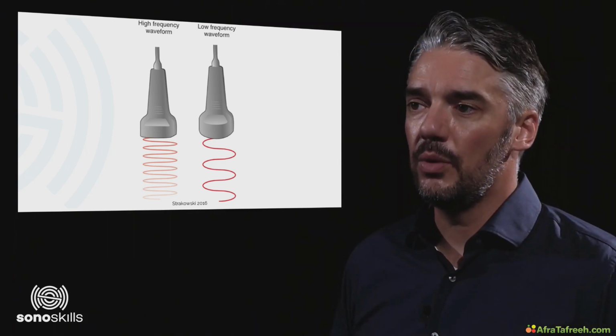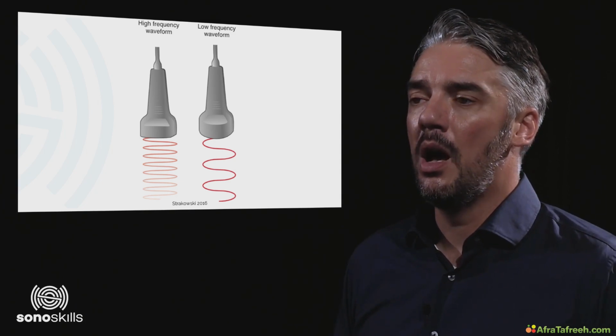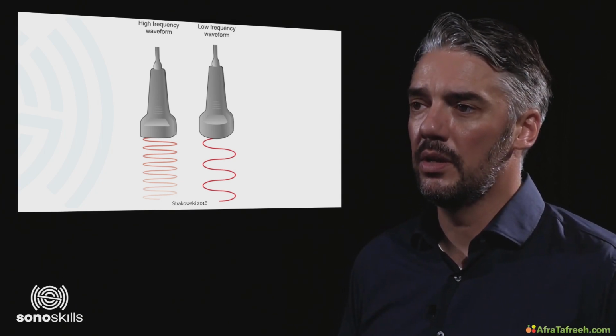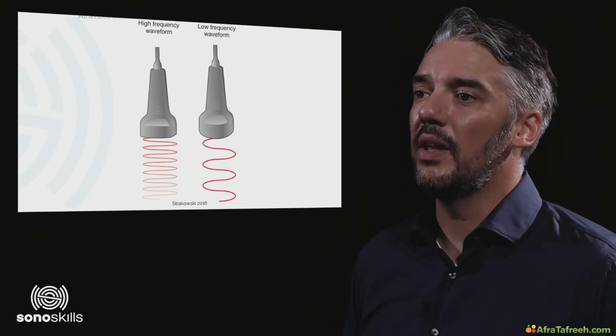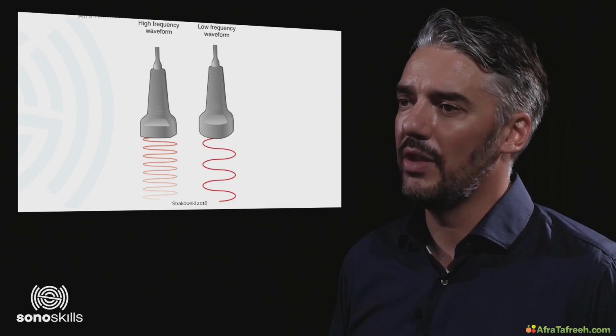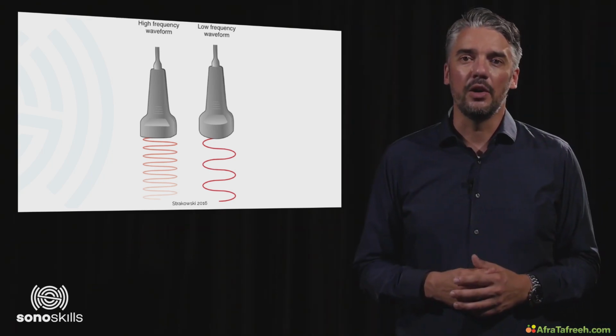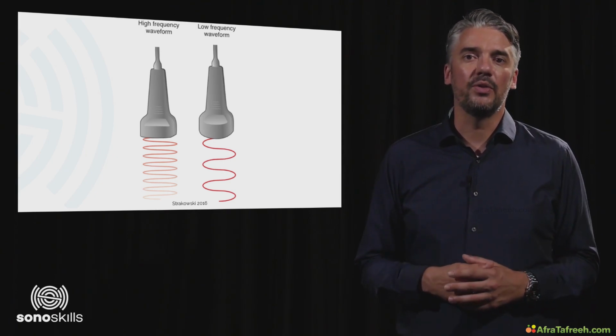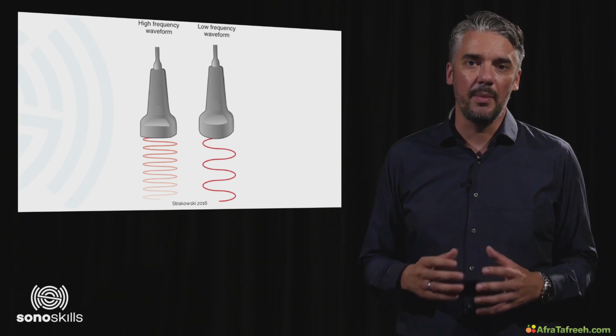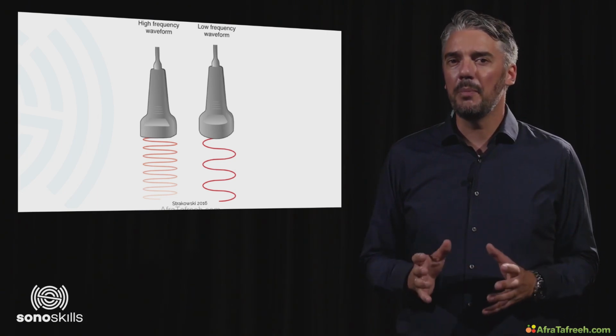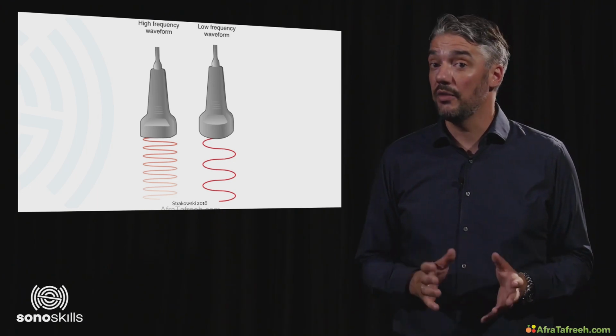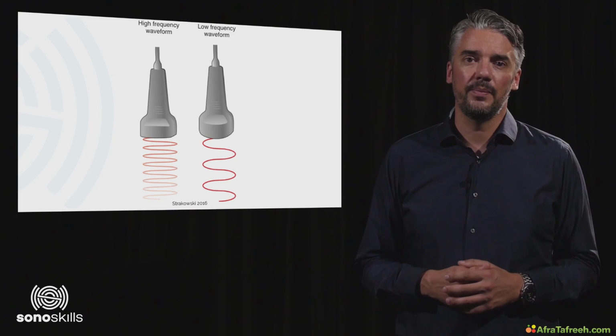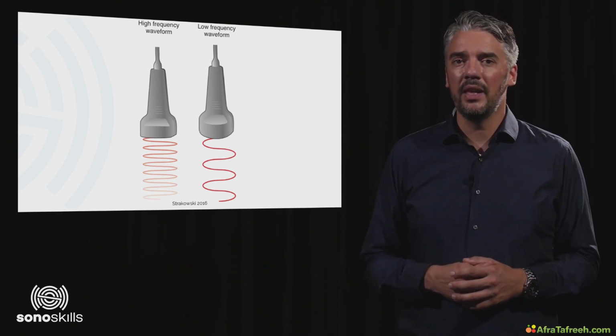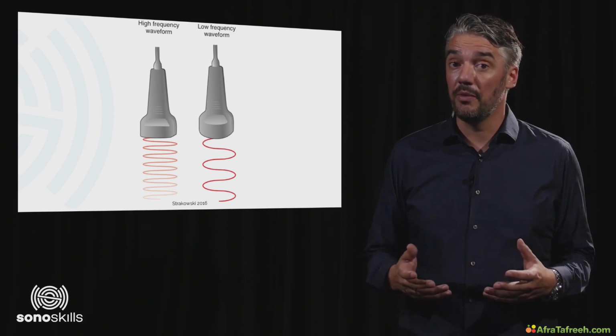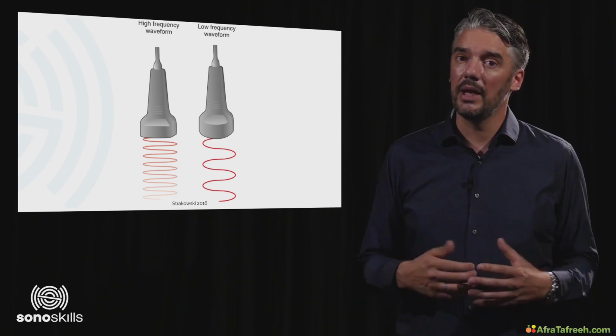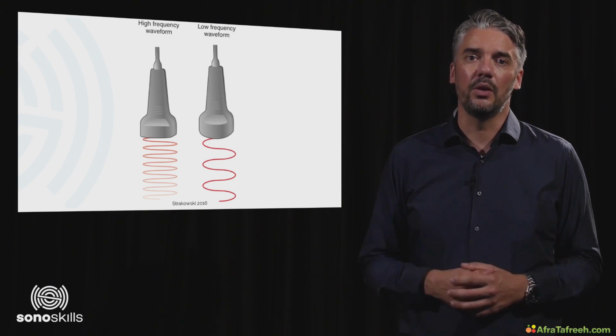In other words, higher frequencies are used for superficial structures. Higher frequencies provide a higher resolution. Disadvantage of higher frequencies is that deeper structures cannot be scanned with high resolution. Lower frequencies are used for deeper structures. Lower frequencies provide a lower resolution. The image is of poorer quality. But the compromise is that it's capable, in contrast to higher frequencies, to scan these deeper structures. As an example, we could state that a median nerve in the carpal tunnel, a very superficial structure, is preferably scanned with 18 MHz and a hip joint with 6 MHz.